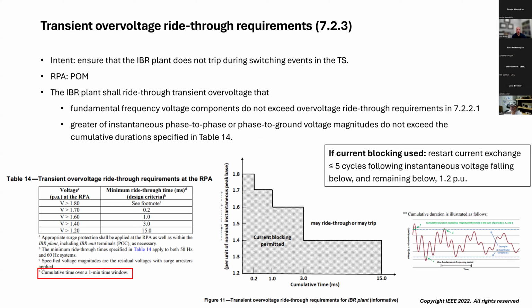Okay, so another requirement. We're moving away from requirements based on fundamental frequency, line to line or line to ground voltage, and now we're going to look at the instantaneous values of the line to line or line to ground voltage. And this is the transient overvoltage ride through requirement. The original intent of this requirement is just to make sure that the IBR plant does not trip for normal switching events on the transmission system. The reference point of applicability is the point of measurement. So there's some coordination that needs to be done to make sure that the IBR units can actually ride through what shows up at the POM.